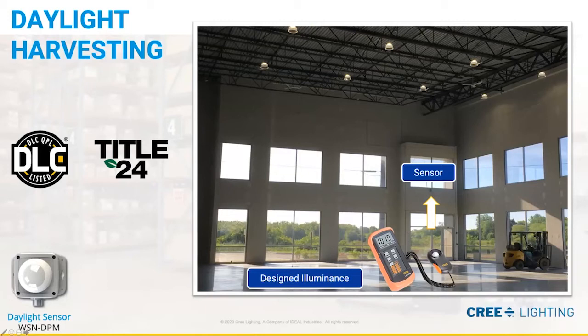So the solution is to use an open loop daylight harvesting system, where the sensor is pointed at the natural light in a skylight or on a window, and then the sensor continuously dims groups of lights in that area while maintaining the designed illuminance in the space. I do have a picture here on the bottom left. This is our daylight sensor that we use in those daylight harvesting applications. I'll talk about that a little more when we get to the hardware section.